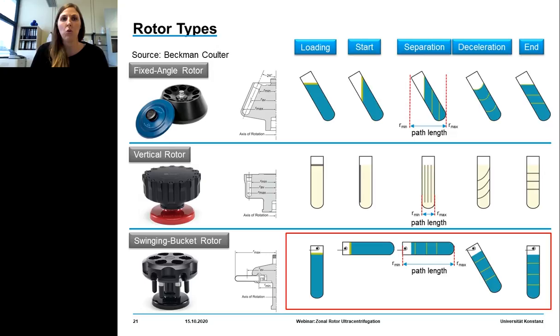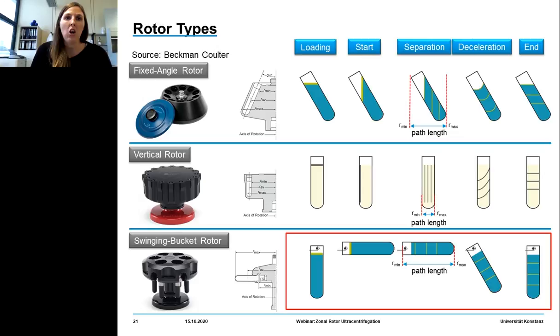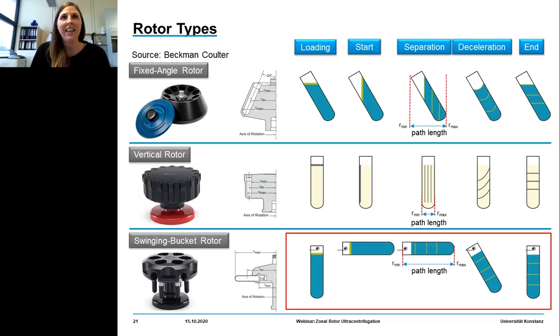For the rate-zonal density gradient method where maximum resolution is needed, excellent separation can be achieved using swinging bucket rotors. Because of the length of the tubes in the horizontal position, sample separation run times are very long due to the increased distance the particles will travel. Additionally, the separated zones remain at the same position in the tube during and after centrifugation, which contributes to excellent sorting efficiency.